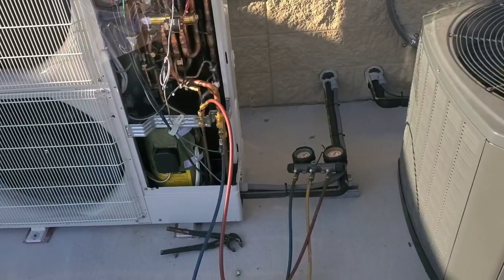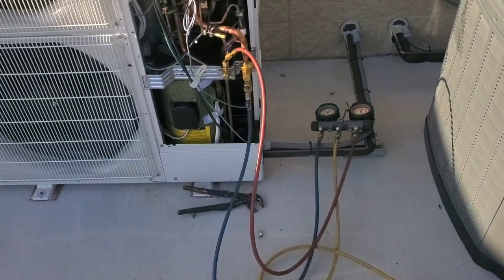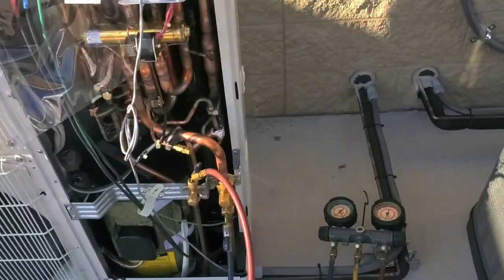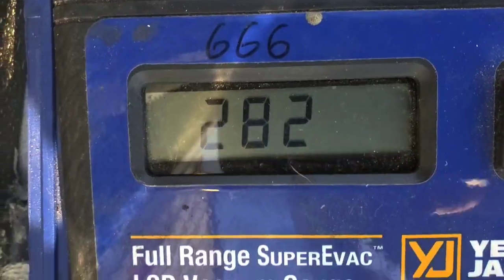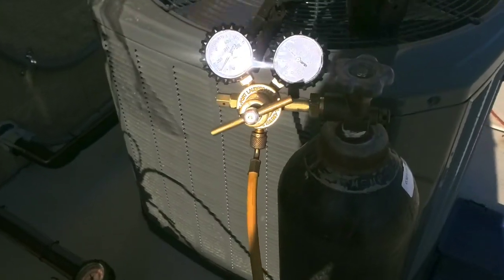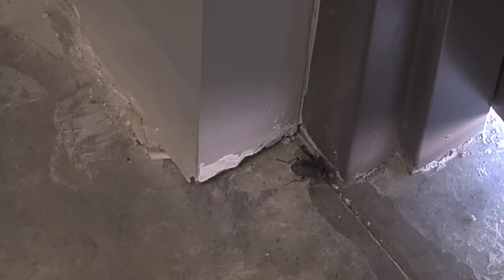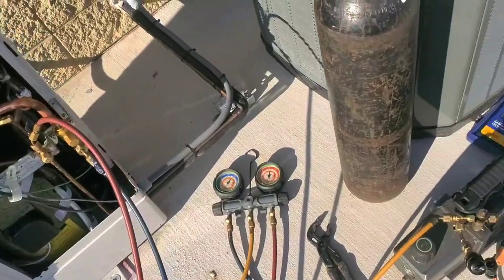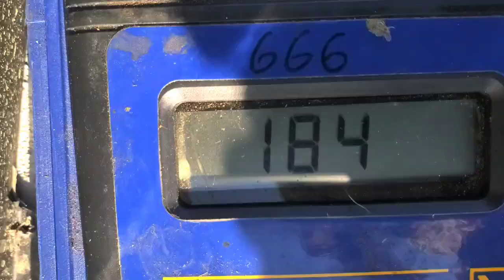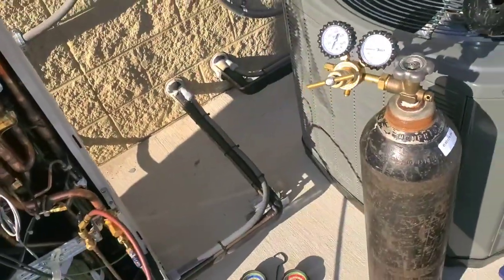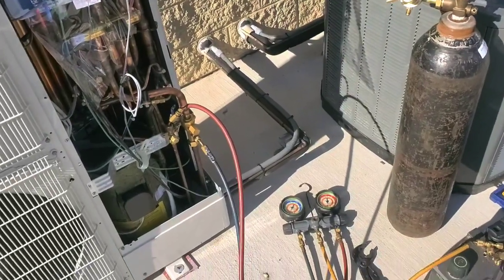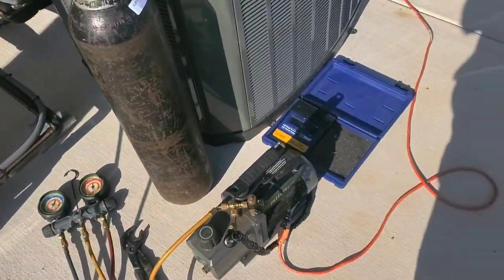So the first of the 3 steps in a triple evacuation is to pull the pressure down to no more than 1500 microns. He's supposed to break it with nitrogen. The second vacuum is supposed to be below 1000. Then you're supposed to break with nitrogen again. So the last vacuum is supposed to be below 500 microns.